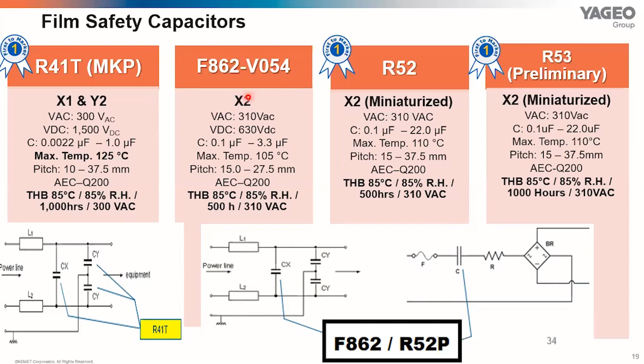EMI caps are primarily responsible for filtering high frequency, high voltage transients, but are not so effective against lower frequency harmonics, typically due to lower capacitance values and lower ripple current possibilities.